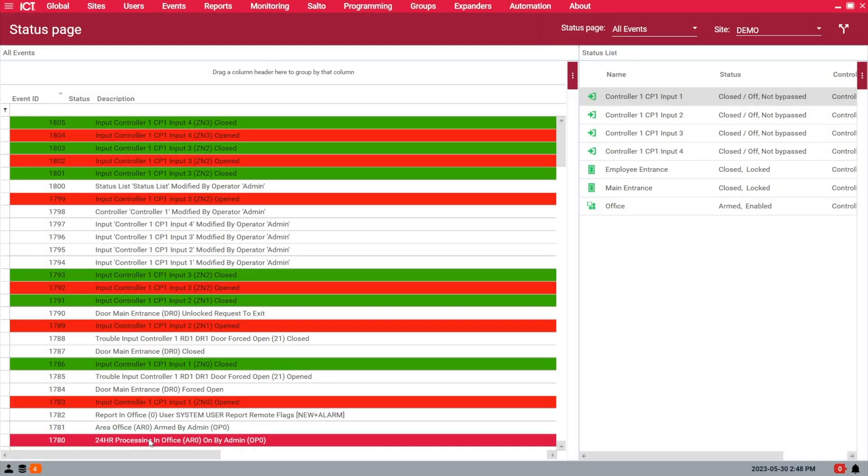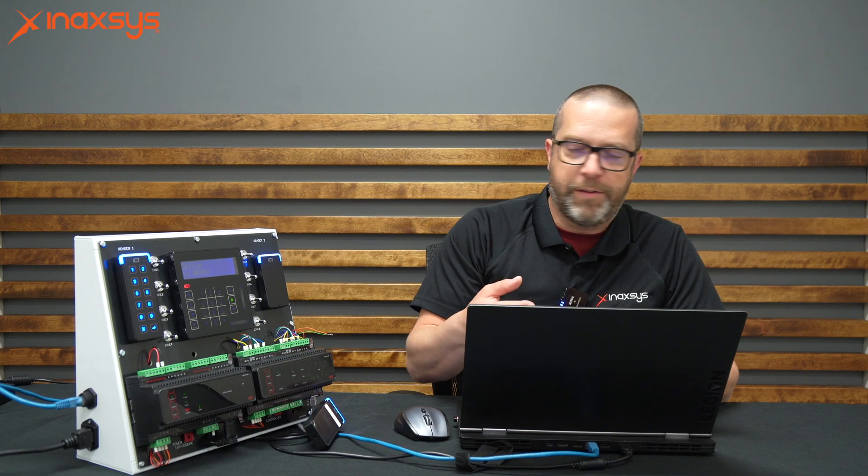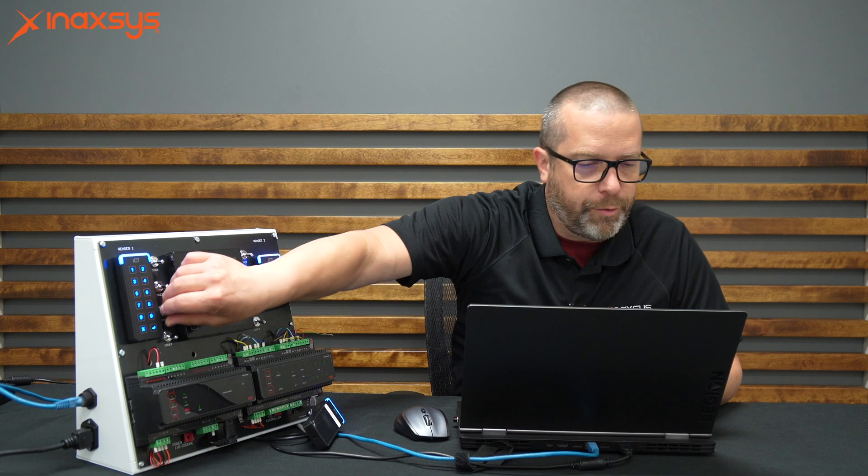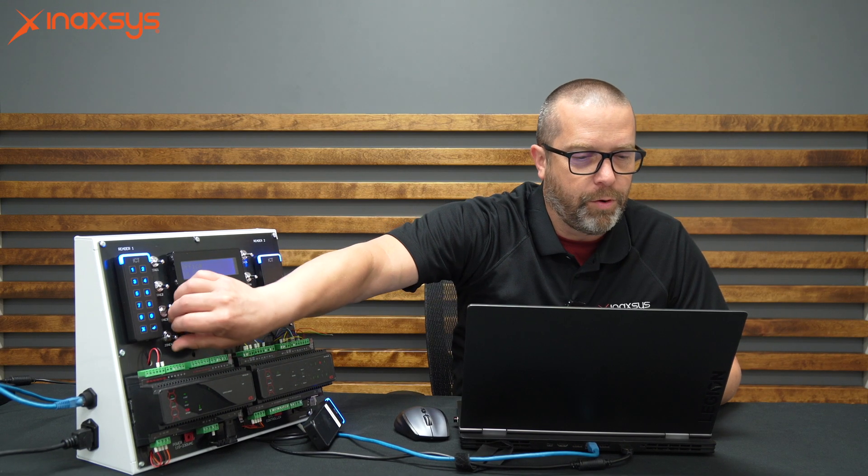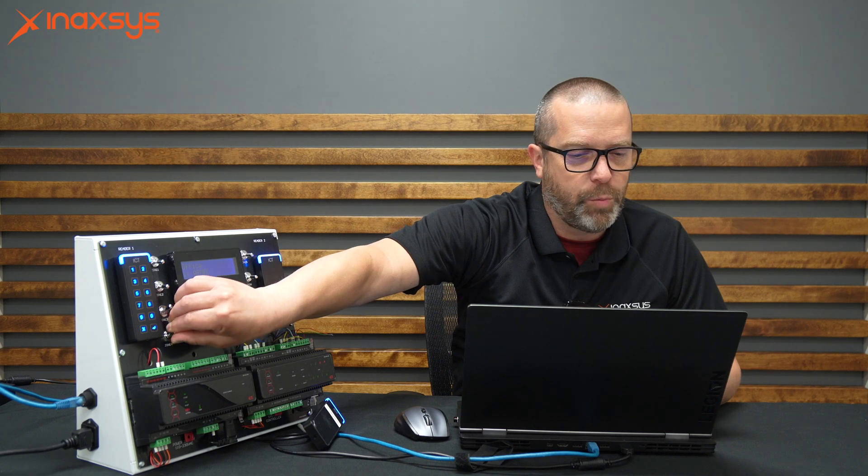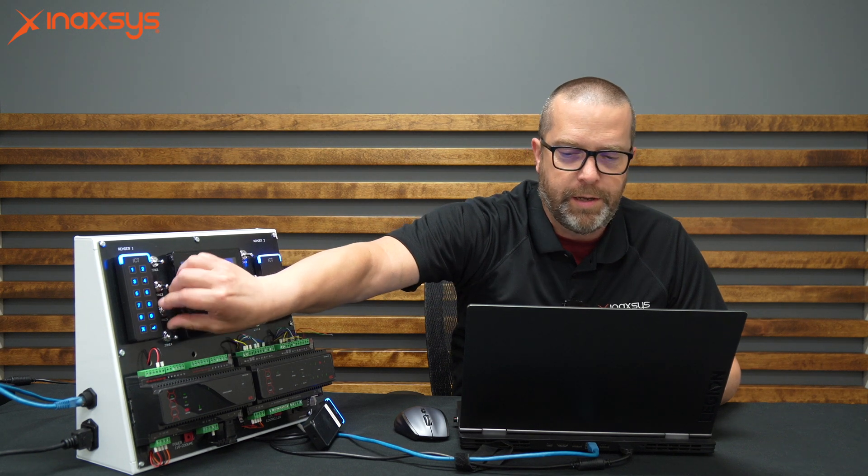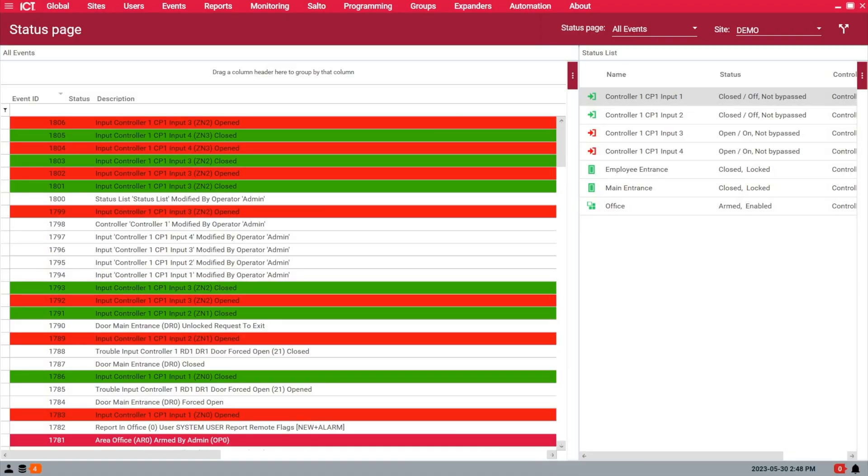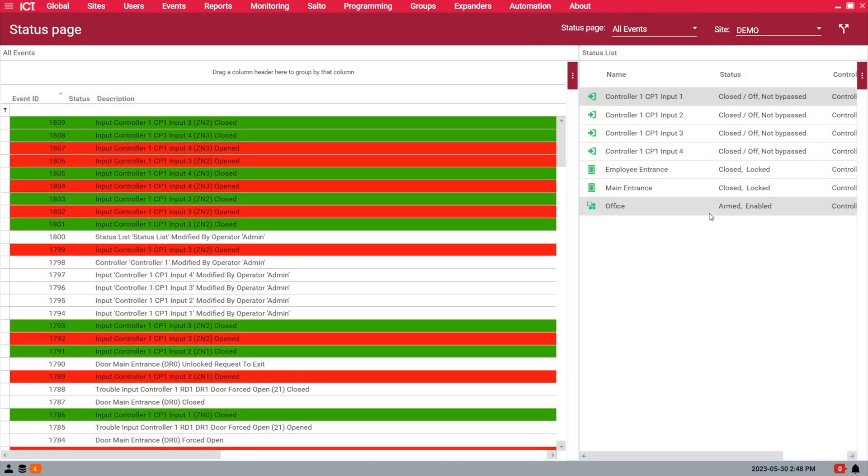Back in the software for this troubleshooting tutorial. You see I have zone 3, zone 4 opening and closing, but on the right side here, the office area is armed but not in alarm. Let's see why. I want to go to the site tab, controllers.